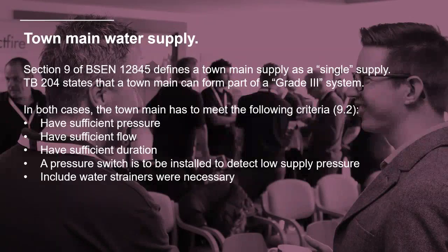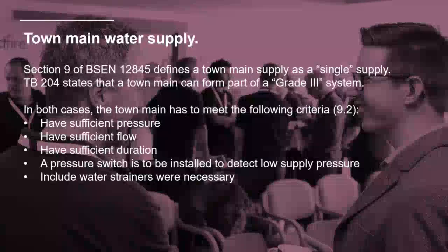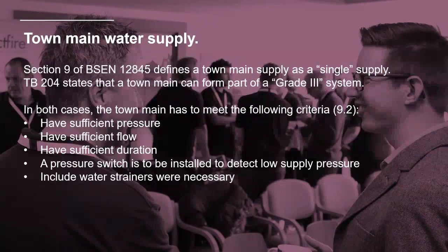It needs to have a sufficient flow. That's often governed by the size of the pipe. A domestic supply may only be a 25 millimeter pipe, so that isn't going to have sufficient flow in a commercial sprinkler system to allow all of the heads in the area of operation to operate at once. That requires a fairly significant flow, so we need a larger sized pipe to achieve that.